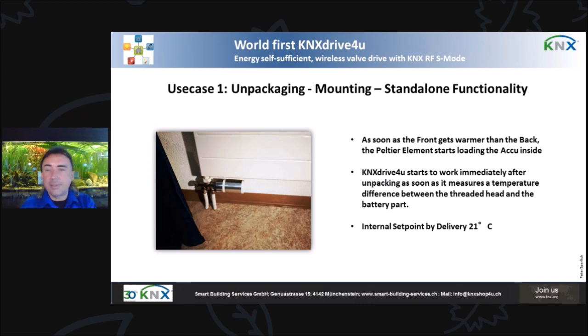And if it's not empty, if it got enough energy through the summer, it's working at once. So the room is not overheated when the heating season starts, because you have the set point at 21 degrees, and it will work at 21 degrees. This works without any programming. You don't have to use the ETS. You just put it in your project on the valve, and you have room temperature regulation inside.